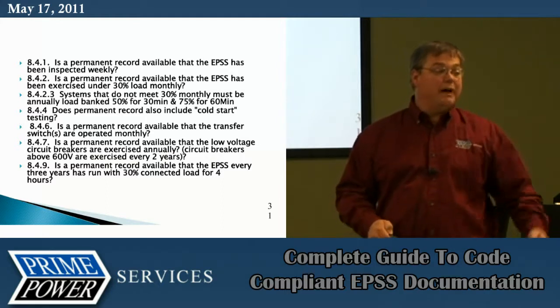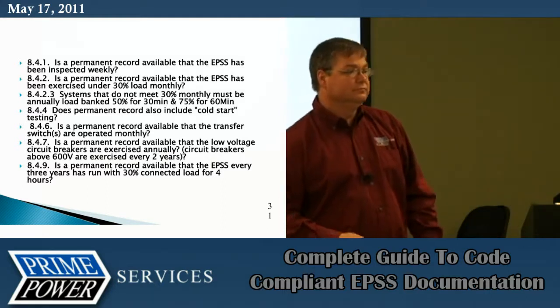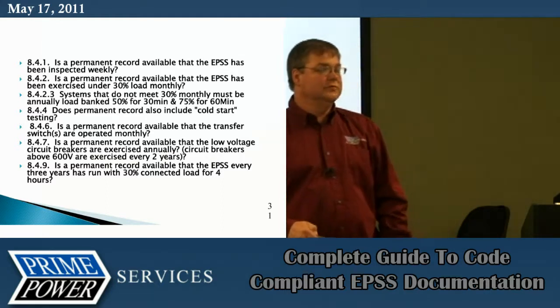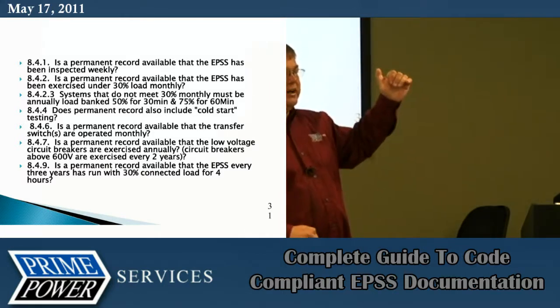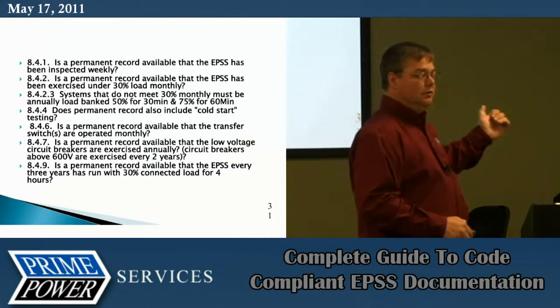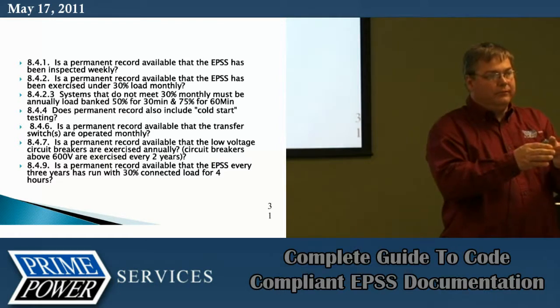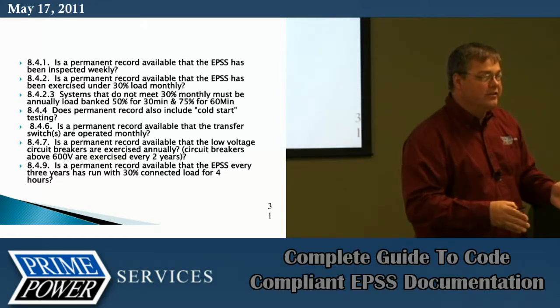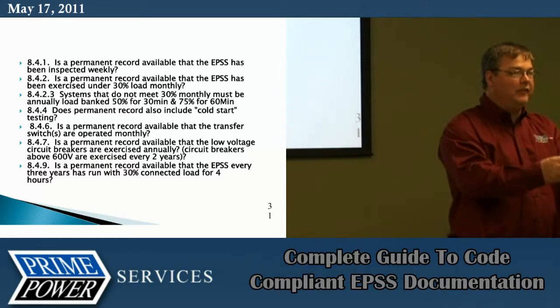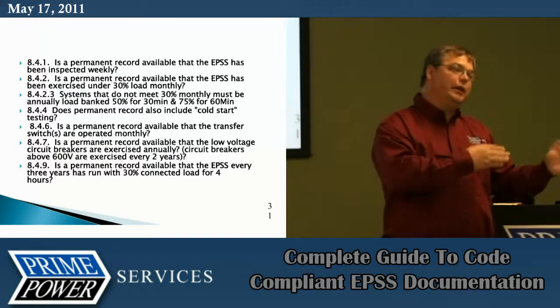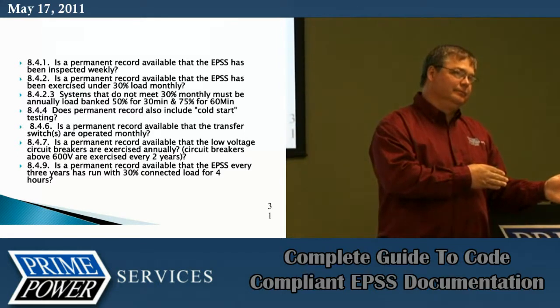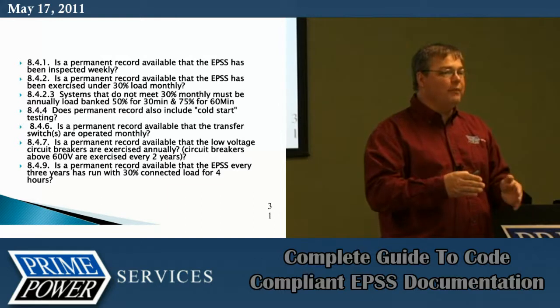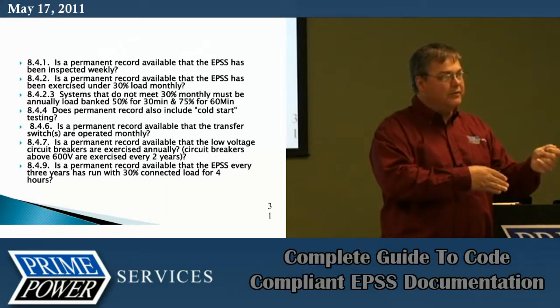They usually do. I would say on your monthly, opening up normal today. No, not opening up normal, transferring over. The intent there is people in the past that have fired a generator up for their monthly purposes and wait to put a load on it. Don't wait to put the load on it. The cold start means fire it up, transfer the load within 10 seconds.